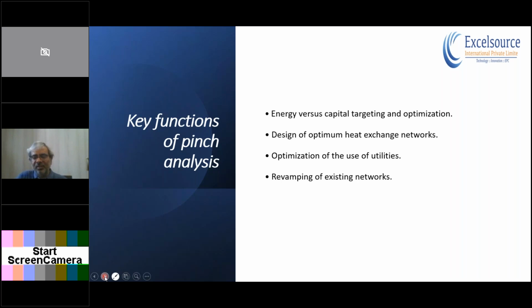So while doing the pinch technique study, what do we have to take into consideration? These are the four factors that we have to consider. First, energy versus capital targeting and optimization. It should not happen that only a small amount of energy is available and we end up with a high amount of investment. Second, design of the optimum heat exchanger network. We should not oversize the heat exchanger so that it becomes unviable or people try to restrict the investments.